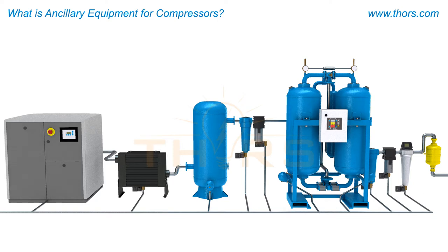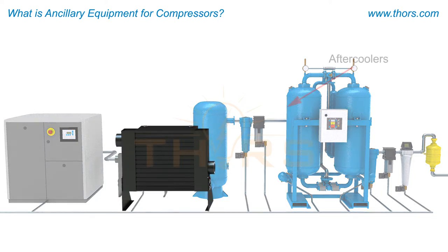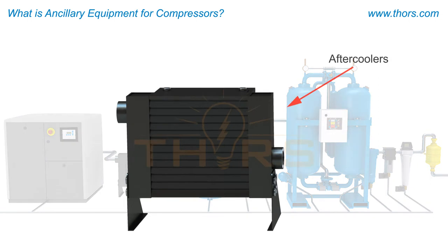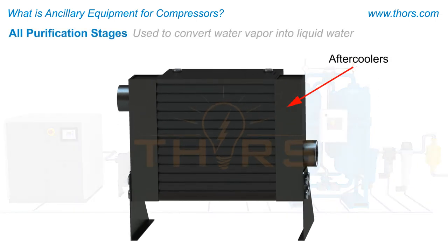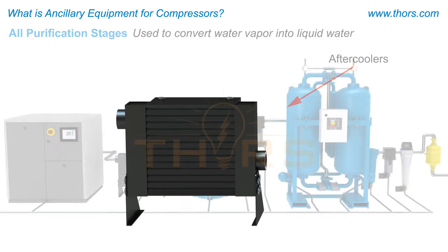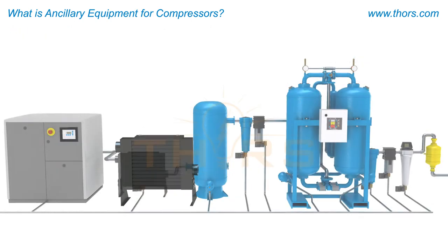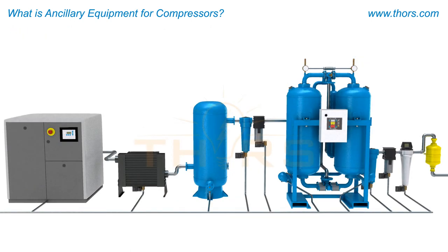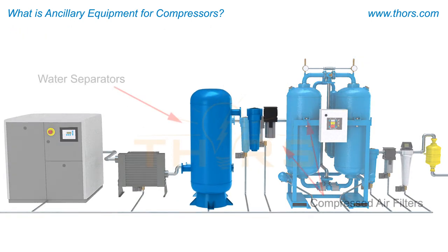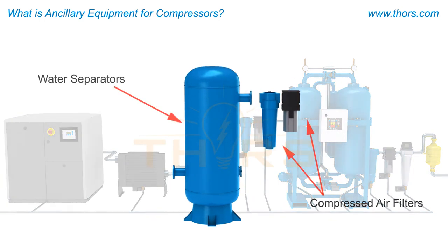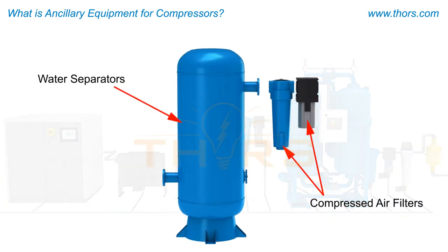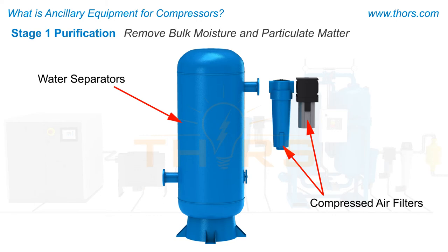After coolers are used in all stages to convert water vapor into liquid water. Water separators and compressed air filters are used during stage 1 purification to remove the bulk moisture and particulate matter from the compressed air stream.